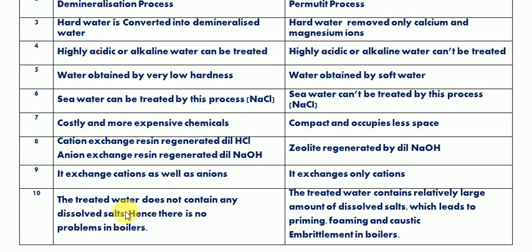The treated water from the ion exchange process does not contain any dissolved salts, so there are no problems in boilers when used as boiler feed water. But in the zeolite process, the treated water contains a relatively large amount of dissolved salts, which leads to priming, foaming, and caustic embrittlement in boilers.